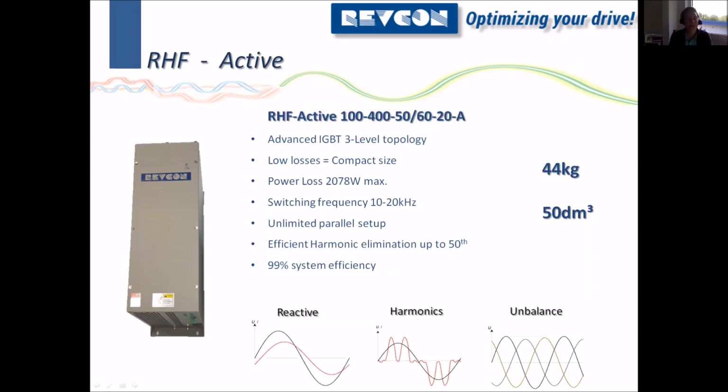Okay, so we have a question. I have a customer who has a great load with laser cutters and the capacitor bank is blowing up. So the capacitor bank is overloaded. Is that correct? And the cables are burning?